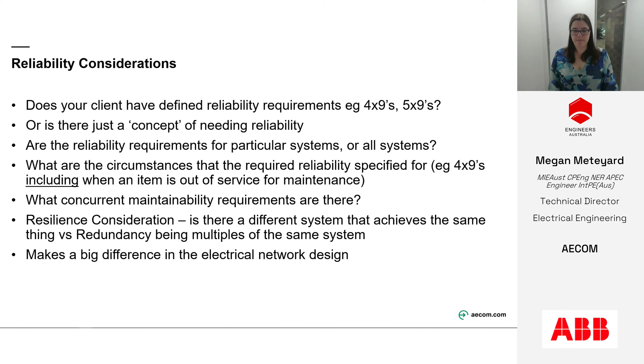So this particular project, I can't tell you what it is specifically, but I can say it wasn't a data center project, and it was a project that had multiple sites where certain reliability criteria was briefed. So in this instance, the criteria stated was 10,000 hours reliability and a 99.99% availability. Now, what that really means, reliability, how long will the system perform its intended function without failure? A 10,000-hour system is about 1.13 years. 99.99% reliability, in this instance, equates to a downtime of about 53 minutes per year. So that was the client criteria.